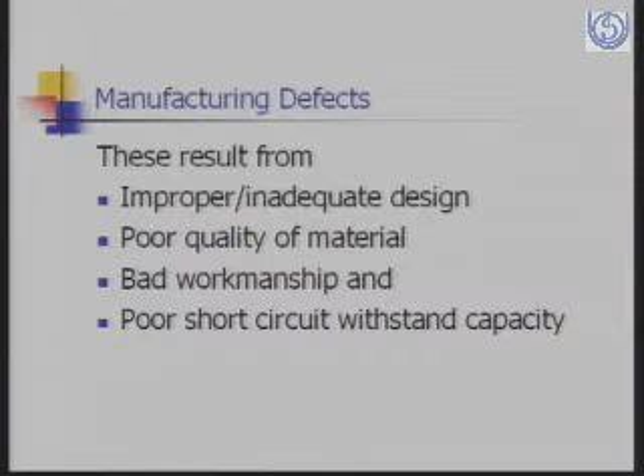So now we will go on to manufacturing defects. These can result from improper, inadequate design, as I said earlier, poor quality of material used, bad workmanship, and poor short circuit withstand capacity. So manufacturing defects like inadequate and poor design, which we discussed earlier, include the transformer tank size. There is inadequate clearance for free circulation of oil. As I said, cost cutting is there, so there is inadequate clearance for free circulation of oil, which causes failures.